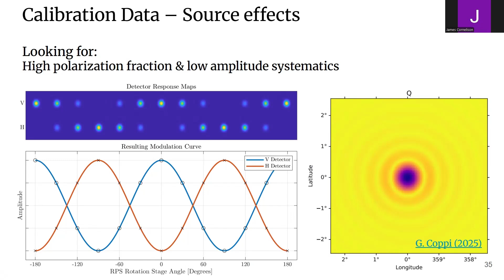There are several considerations when thinking about the source output. First, CMB beams are broadband. Our instruments collect photons over a wide frequency range, and the beam shape varies across that range. The actual beam is the frequency-weighted average of all of those little beams. So the source either needs to be broadband as well, or we need to take multiple beam maps at different frequencies to reconstruct the true beam. Second, the source must be bright enough to give good signal to noise, but not so bright that it saturates those incredibly sensitive detectors. And of course, the source output needs to be stable across the entire observing period.